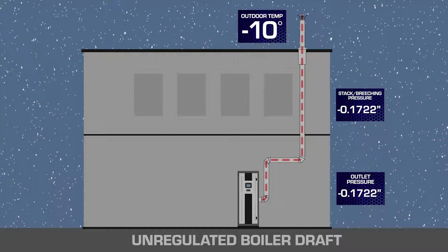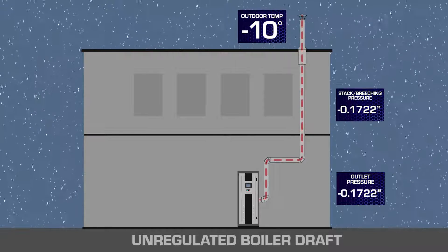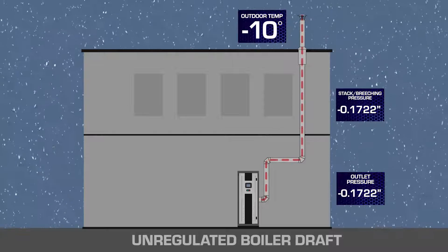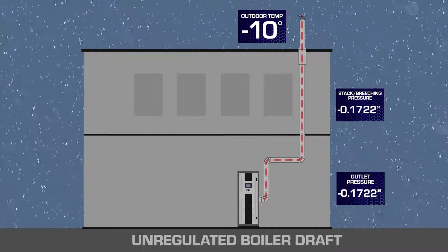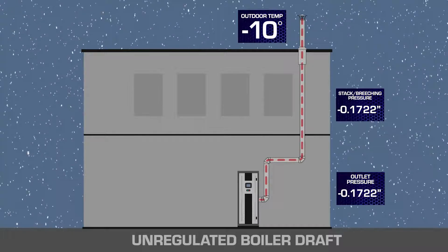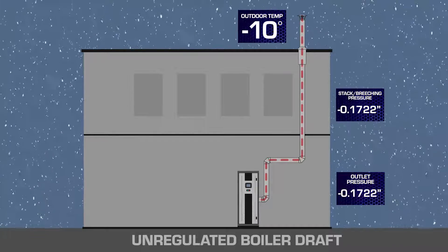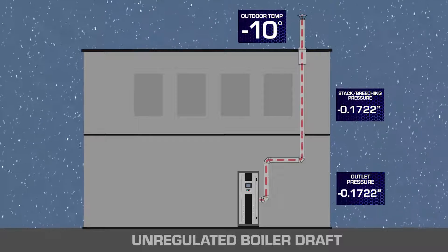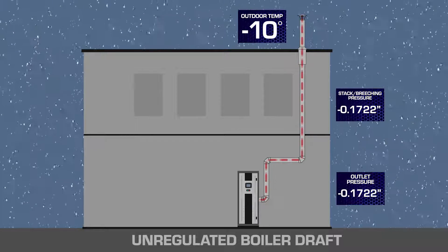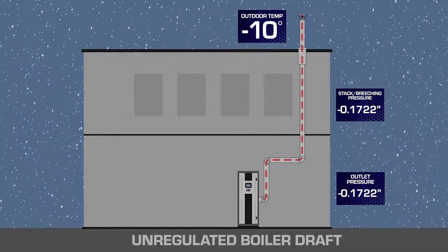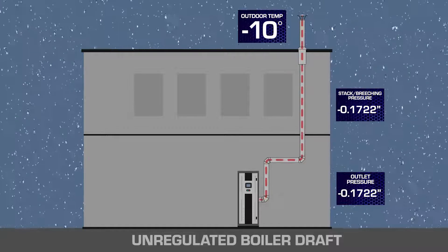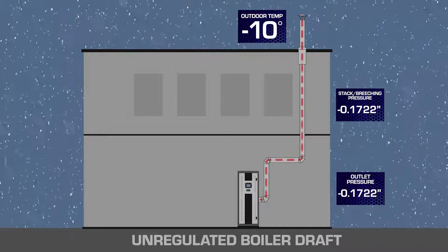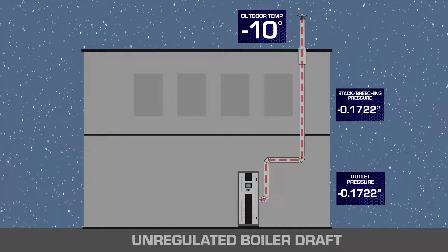Second, we need to make sure we stay inside the appliance's maximum negative outlet pressure range. This is done at a low ambient temperature, maximum draft scenario, and low firing rate. If the appliance outlets go negative, we are now in Category 2 operation, which means loss of efficiency and flame instability.